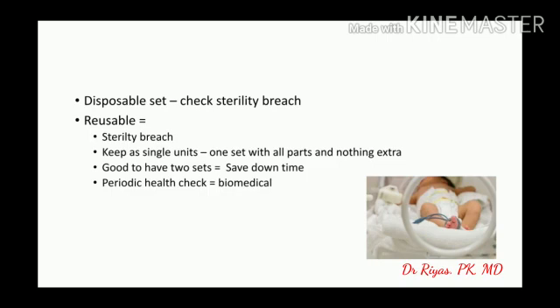And in case of reusable ones, check for sterility breach, and it is always better to keep a single tubing set in separate packs rather than keeping all the tubings in one bin. A pack should contain all the parts of the set and nothing extra. It is also good to have two sets for each ventilator so that we can save downtime, especially when you need to use it for another baby before the tubings are ready after sterilization procedures.